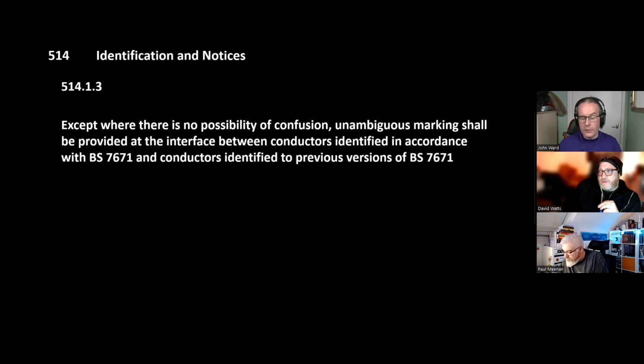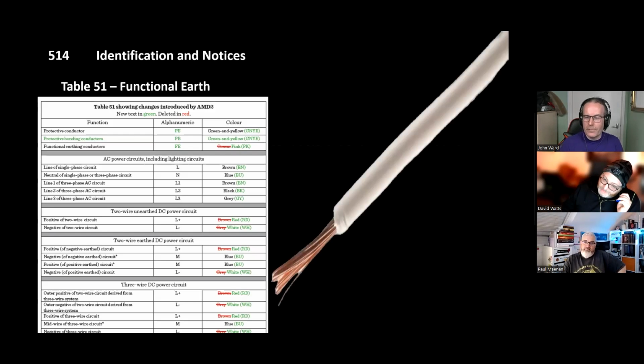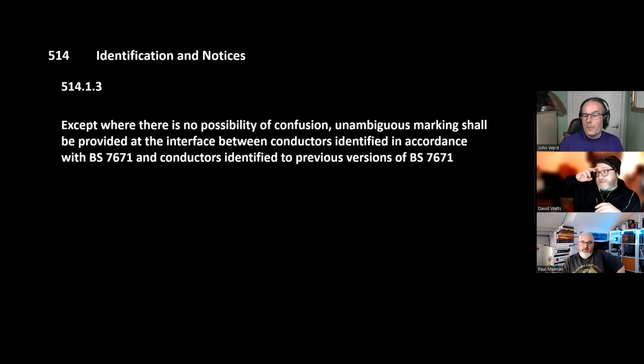So this is where you had your old colours, red, yellow, and blue, and now we've got new colours, which aren't new anymore because they've been out for far too long. This is basically the regs just saying to us we're old now, isn't it? Yes. So basically, mark the cables where they are joining together. It doesn't actually say mark them with colour, so you could have numbers or letters, as long as there's some kind of marking on it. That's kind of the point there.